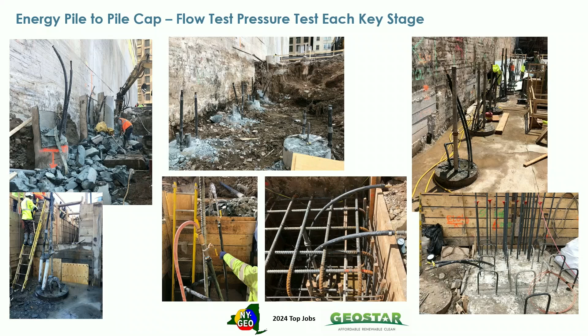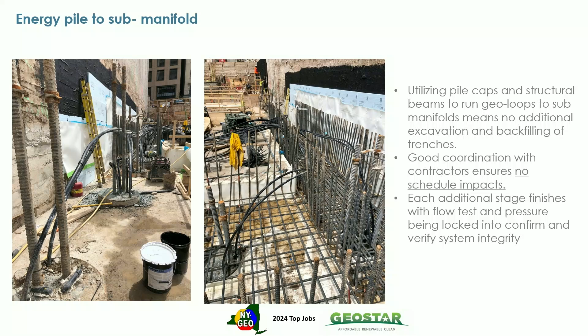What you're seeing here is that they then trim the piles down, as you see in the bottom left. Then we connect each of those piles and run them to the sub-manifolds through the existing structure, so there's no additional excavation for trenching and the horizontal loops. We're using exactly what's already being constructed to form the basement slab here.